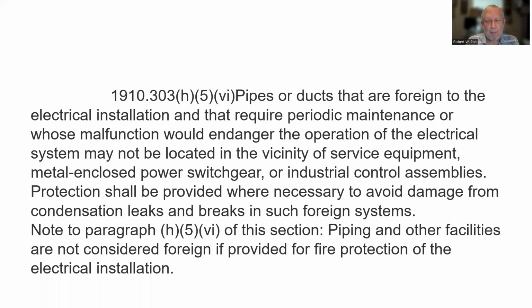Good idea. Pipes or ducts that are foreign to the electrical installation and that require periodic maintenance or whose malfunction would endanger the operation of the electrical system may not be located in the vicinity of service equipment, metal enclosed power switchgear, or industrial control assemblies. Protection shall be provided where necessary to avoid damage from condensation, leaks, and breaks in such foreign systems. Note, piping and other facilities are not considered foreign if provided for fire protection of the electrical installation.